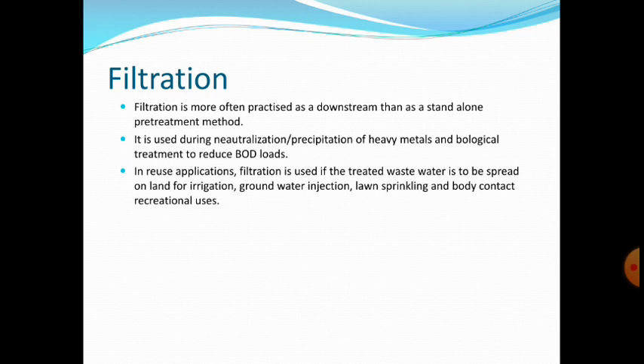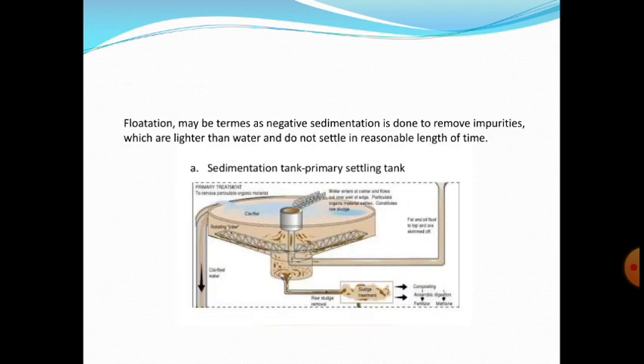Next is flotation, which may be termed as negative sedimentation. It is done to remove impurities which are lighter than water and do not settle in a reasonable length of time. Like coagulants in sedimentation, flotation may be done with or without the aid of flotation agents. Industries employing flotation include woolen mills, slaughterhouses, pulp and paper mills, oil refineries, and dairies. Both sedimentation and flotation help reduce the solid load on downstream treatment units.